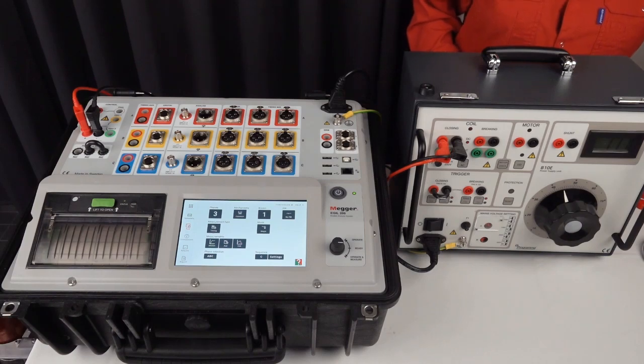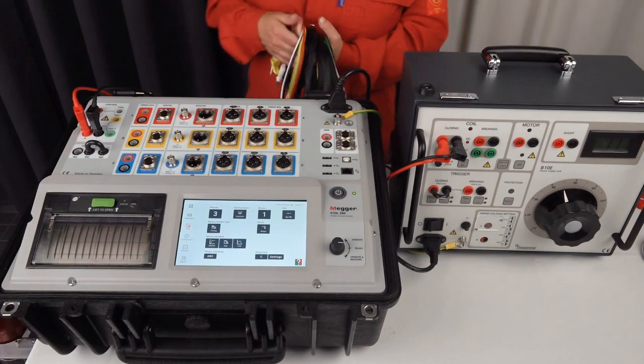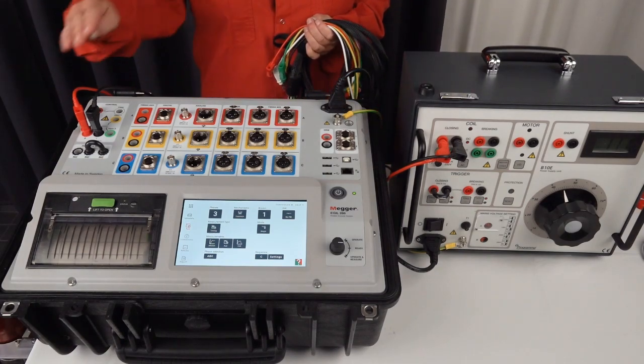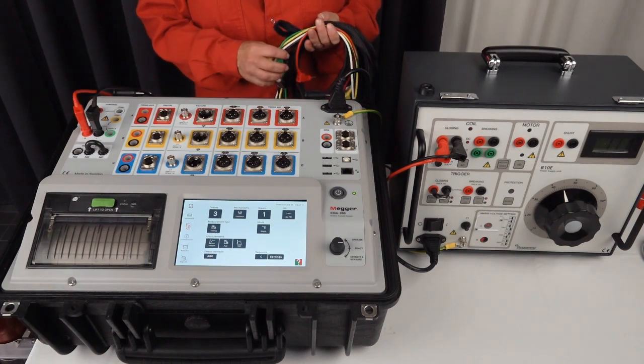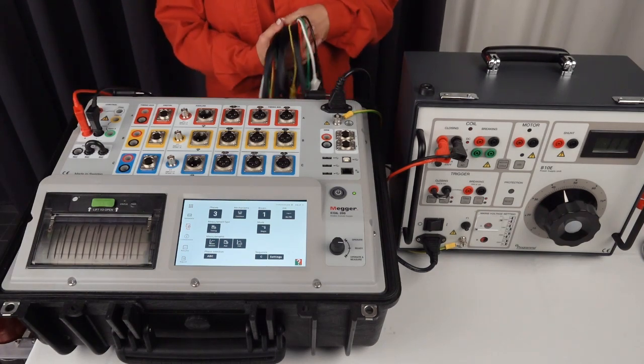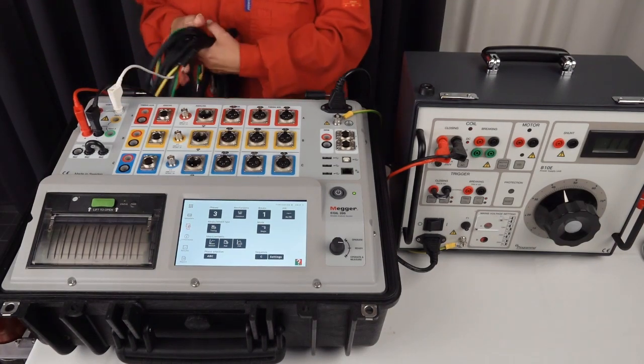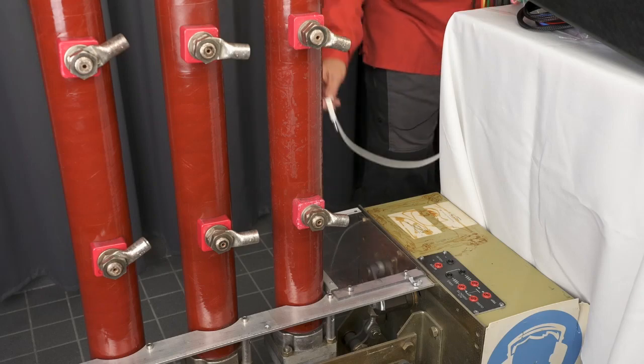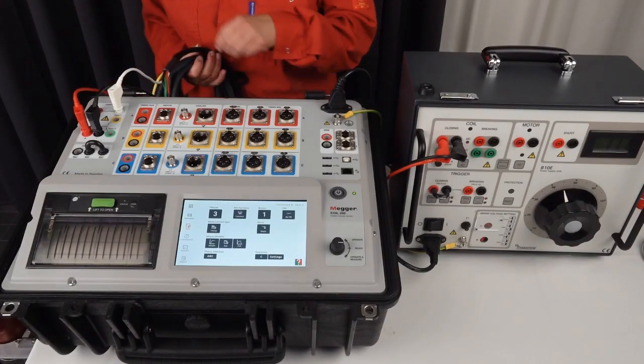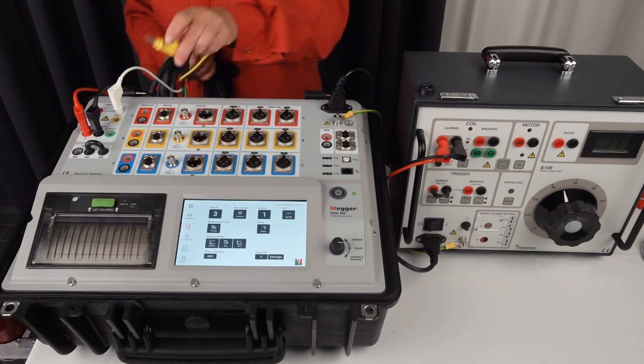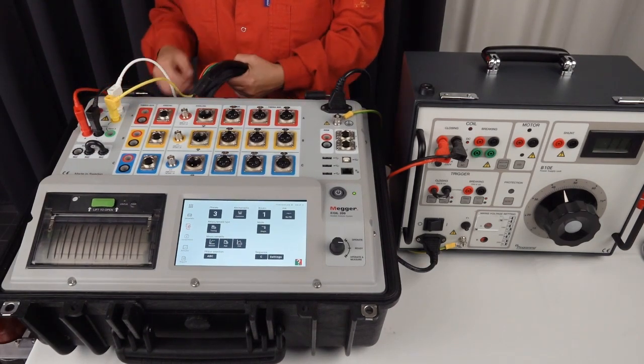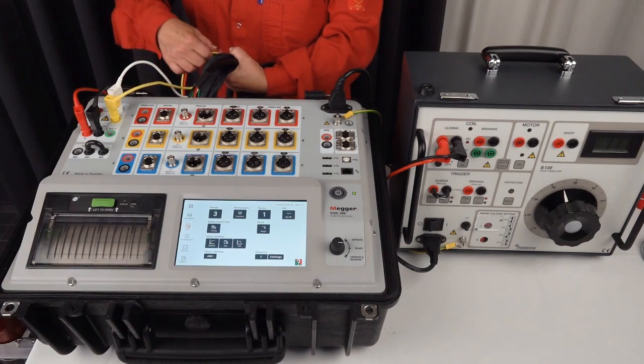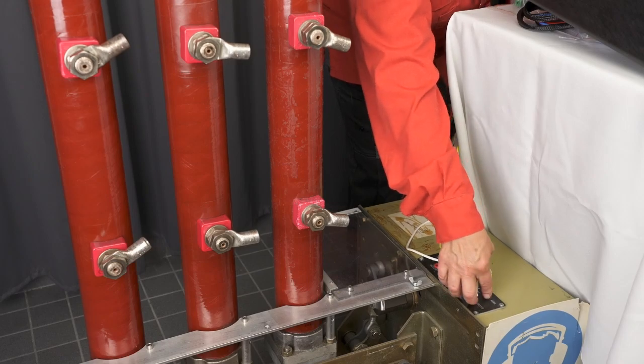I continue with the rest of the connections for the control. The plus and the minus here creates the pulse to operate the circuit breaker. I connect close at the analyzer and close at the circuit breaker. I connect open at the analyzer and open at the circuit breaker.